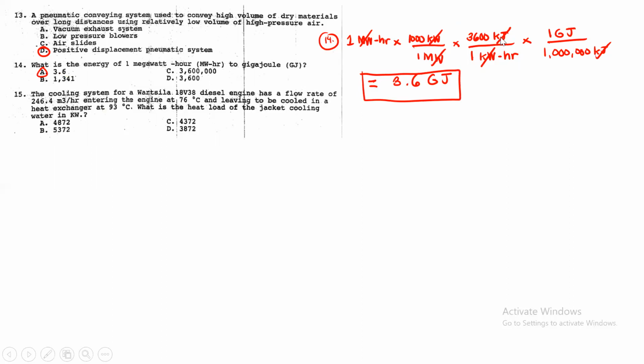So, 15. The cooling system for our Wärtsilä 18V38 diesel engine has a flow rate of 246.4 meter cube per hour, entering the engine at 76 degrees Celsius and leaving to be cooled in a heat exchanger at 93. What is the heat load of the jacket cooling water in kilowatts? So, syempre ito, madali lang itong 15. Q is equals to MC delta T lang.